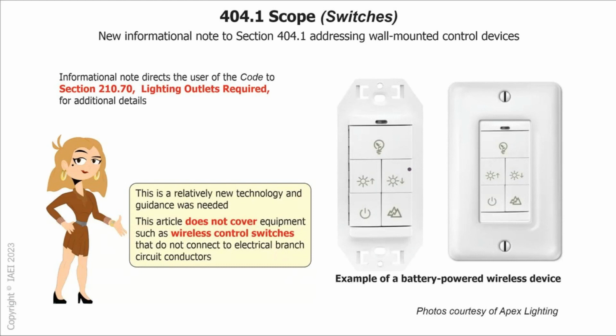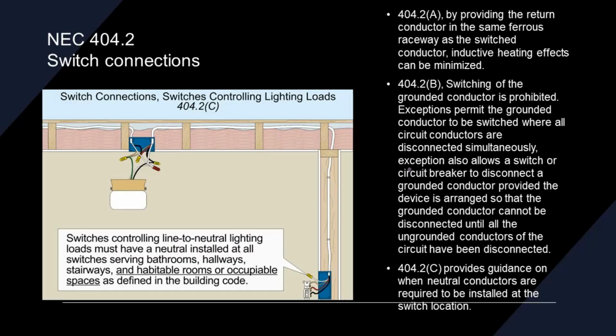This is what they're looking like. I can control multiple lights from one location, things of that nature. And so the code's starting to address some of this stuff. 404.2, switch connections. Basically telling you that you have to have a neutral at most locations in habitable rooms or occupiable spaces.